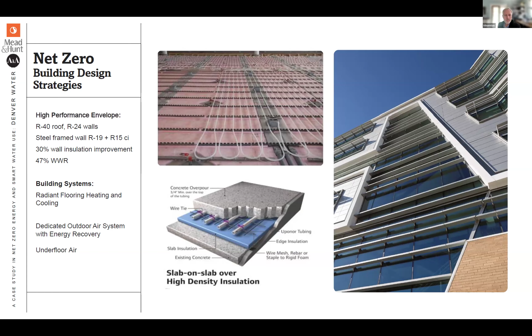But ultimately, it's part of a holistic system. We do have super insulated walls - it's a metal panel system, where I see our numbers don't quite add up there. It's supposed to be R34 walls and R40 roof. There's a steel frame behind it. The panels themselves are interlocking insulated metal panels. The window to wall ratio is around 47%, with some extra windows in some key spaces that we needed to highlight. And then I mentioned earlier that we had a dedicated outdoor air system that happens through underfloor air distribution.